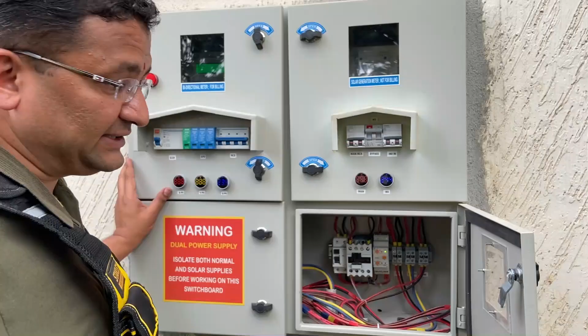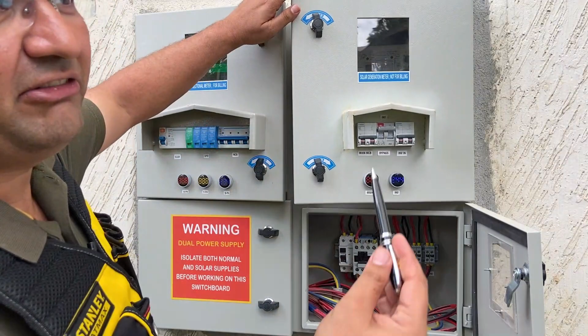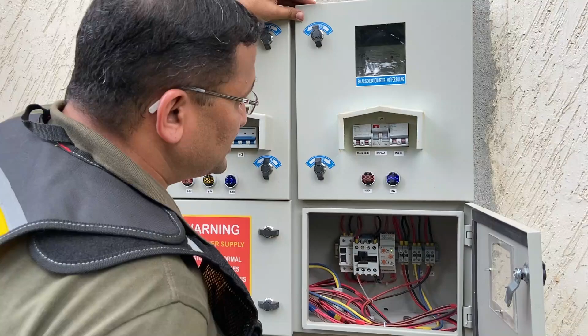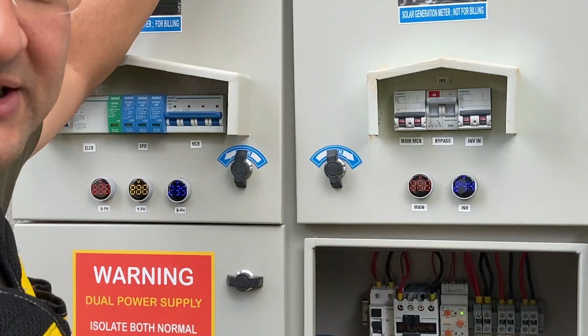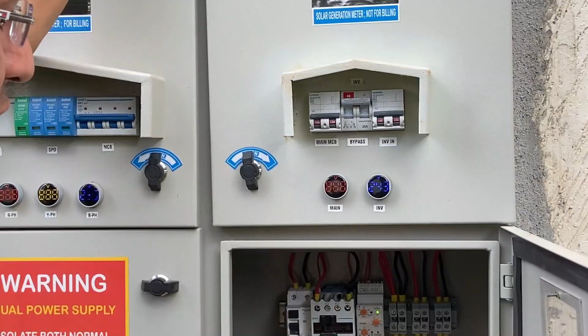The output from that inverter also comes here. Okay, so there is a meter here which actually records the output from the inverter. We also have MCBs here for protection. There is also a changeover switch. Now this is in inverter mode. In case there is a fault in the inverter, we can actually bypass it and run it even directly from the grid. If one needs to switch off the power completely, if this goes to the center, the power is off. So this is about the hybrid system that we have installed at this site.